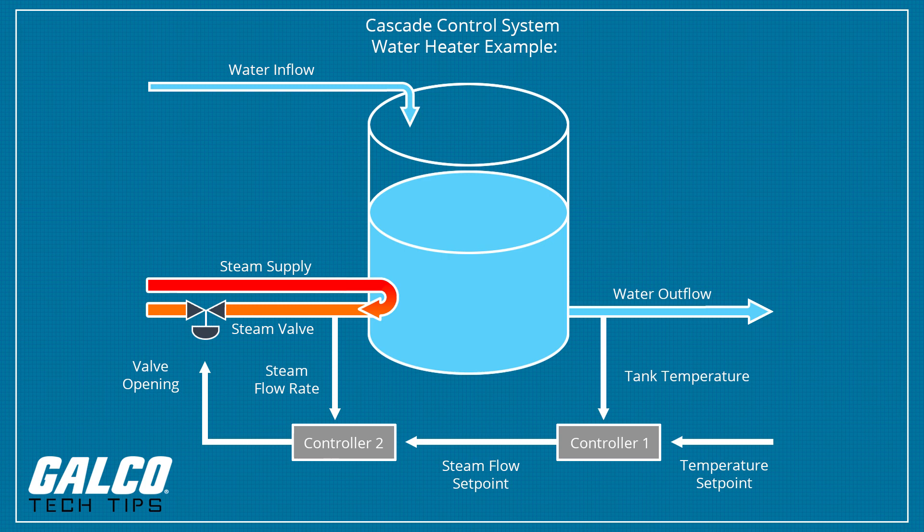In this example, the primary controller's output determines the setpoint for the secondary controller. The secondary controller's output is then used to adjust the control variable. The secondary controller will generally change quickly while the primary controller changes slowly.